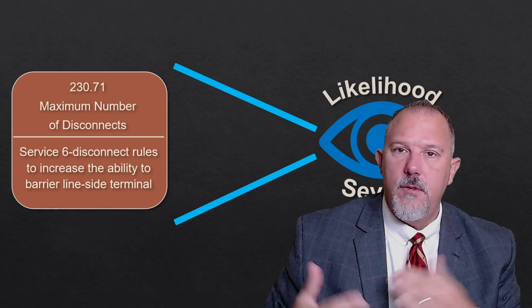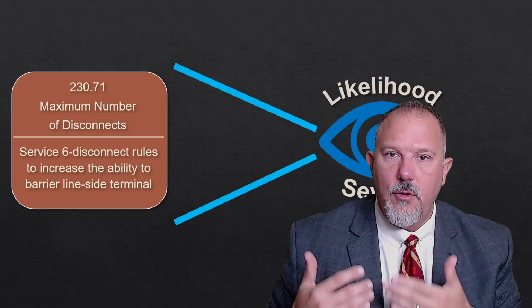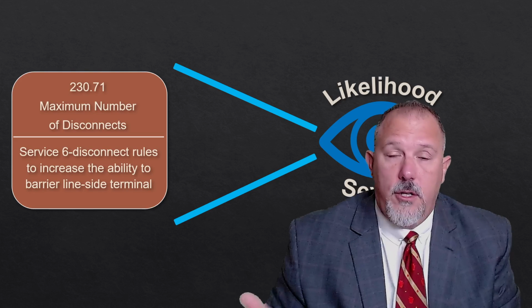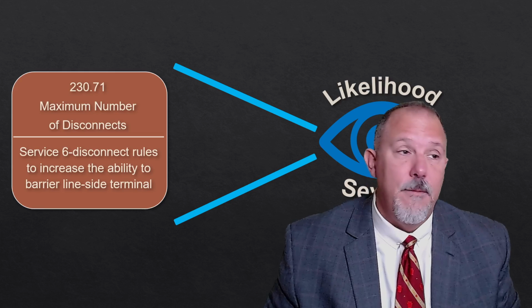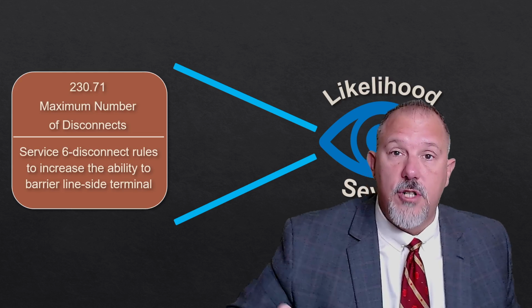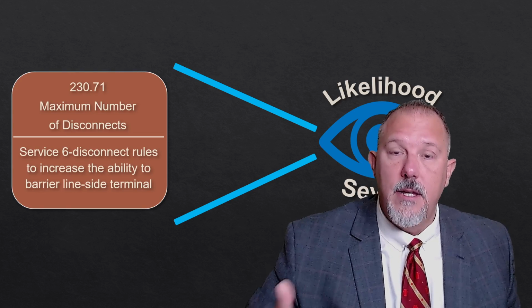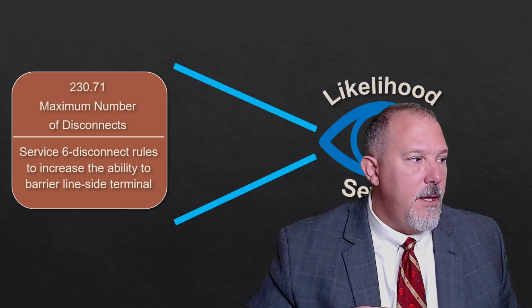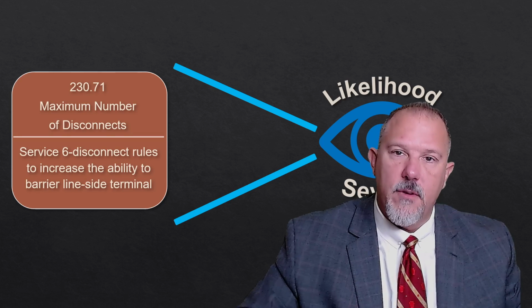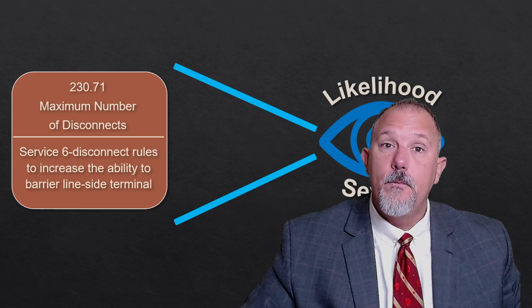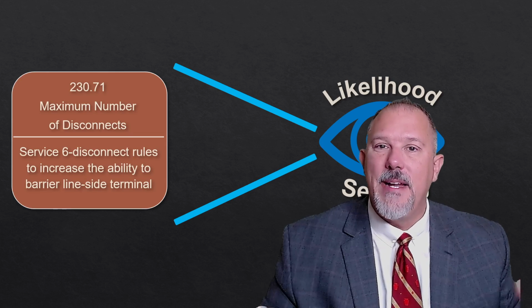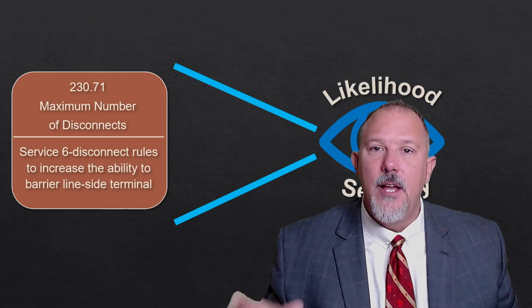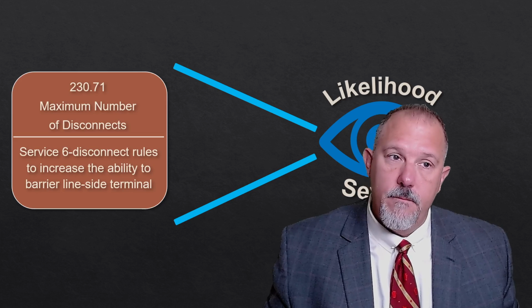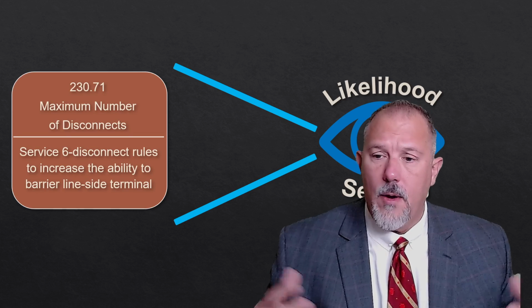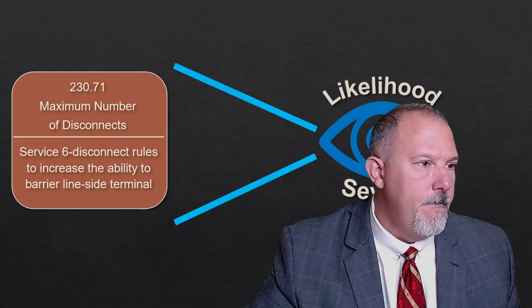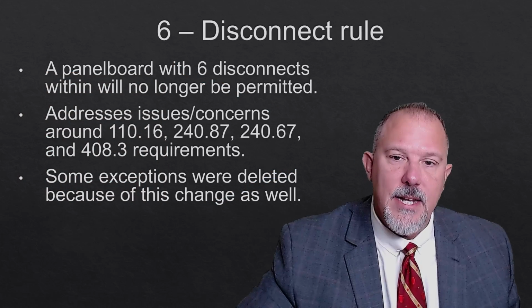So there may be a lot of different reasons why you can't establish an electrically safe work condition, including testing. I mean, that's like the number one reason you would do justified energized work, if you're testing and doing things like that. But when I can provide an ability to isolate power within my power distribution system without impacting a wide area of, say, tenants or rooms or applications, better off I am.